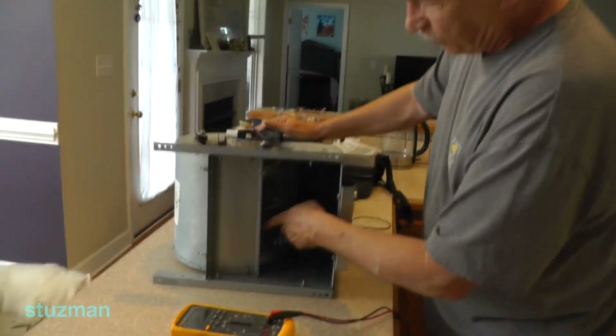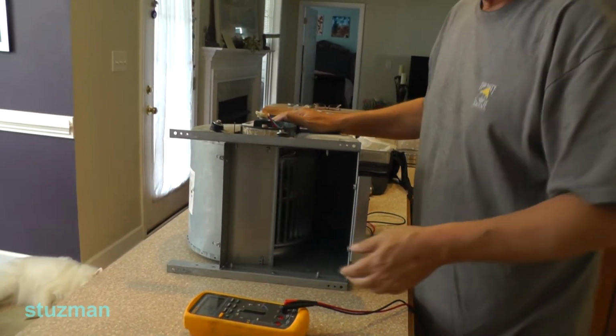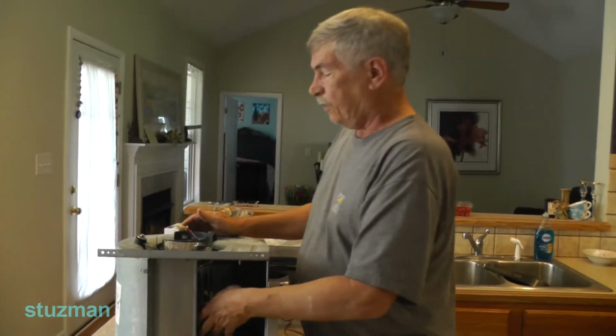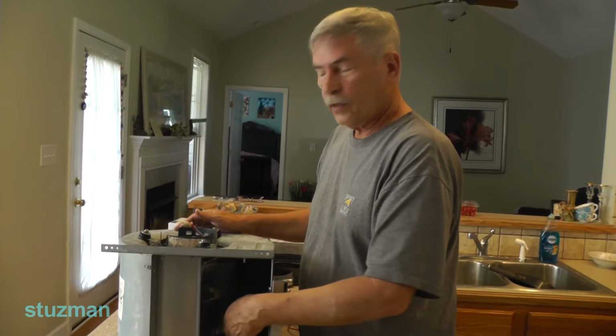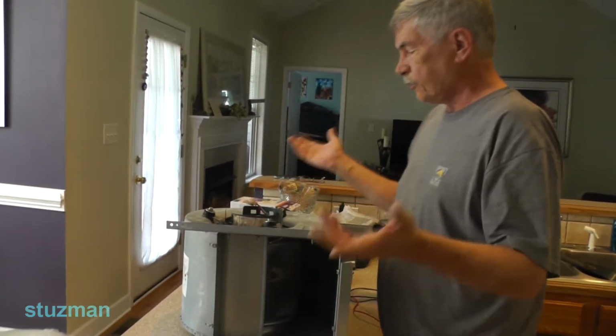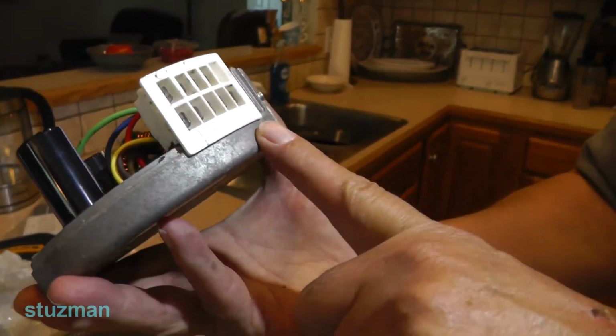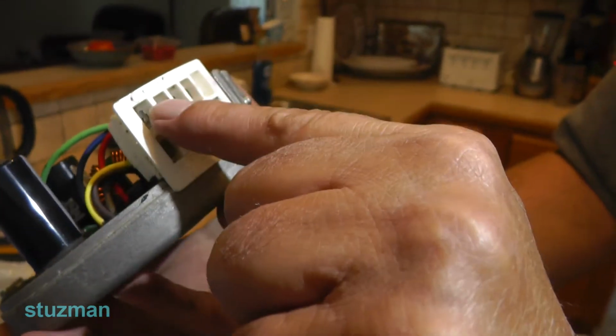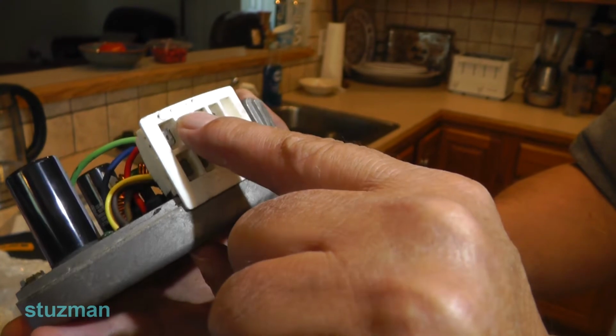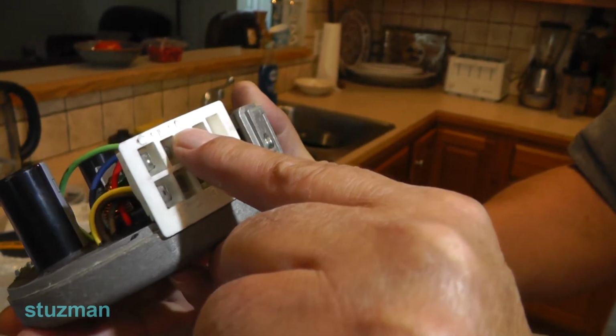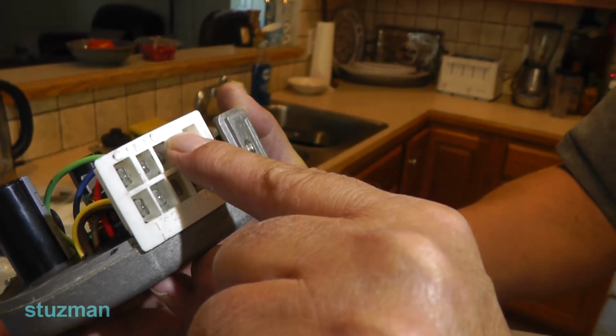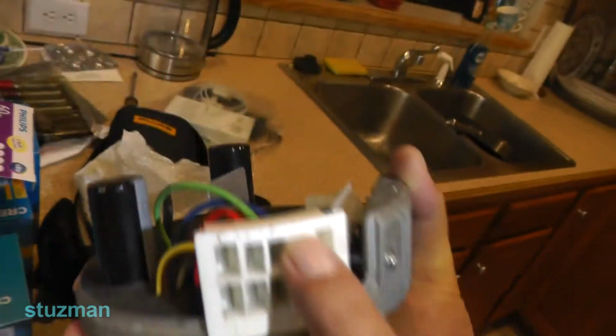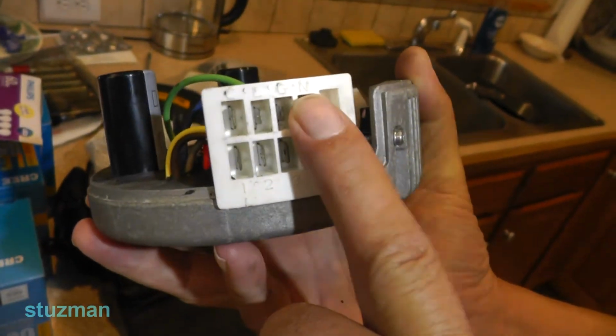Also, like I said, we covered it before, right? You got any bad bearings? Bearings are in here. This one all seems pretty good, okay? So that looks good. Now going back to this, we'll talk about this a little bit. If you look up here, you can see that it's marked. You got your line power, you got a G for ground, you got N, which is neutral. Now, some of these motors actually can come at 120 volts.